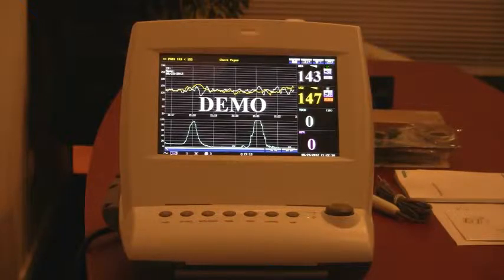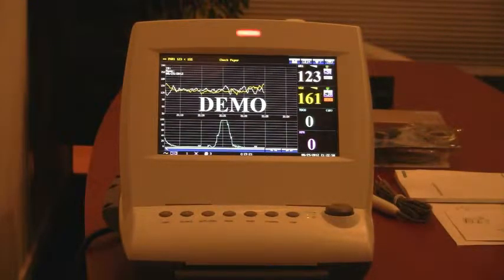It's got a fetal heart rate measuring range of 50 beats per minute to 240 beats per minute. It utilizes a 1 megahertz waterproof sensitive transducer. It's got signal overlap verification to differentiate between the twins' fetal heart rates, and a fetal heart rate quality signal indicator as well, to make sure that you've got proper probe position.